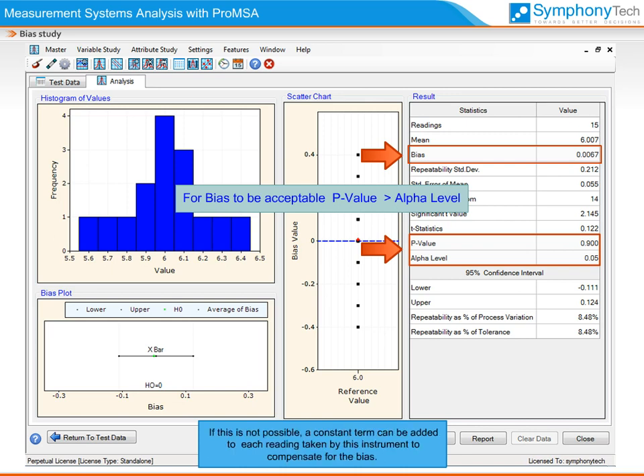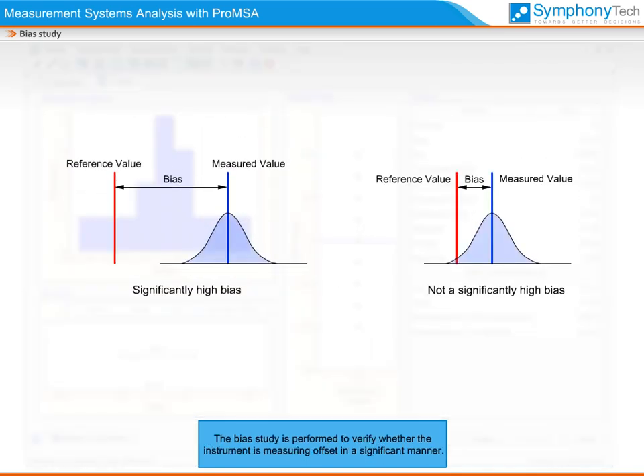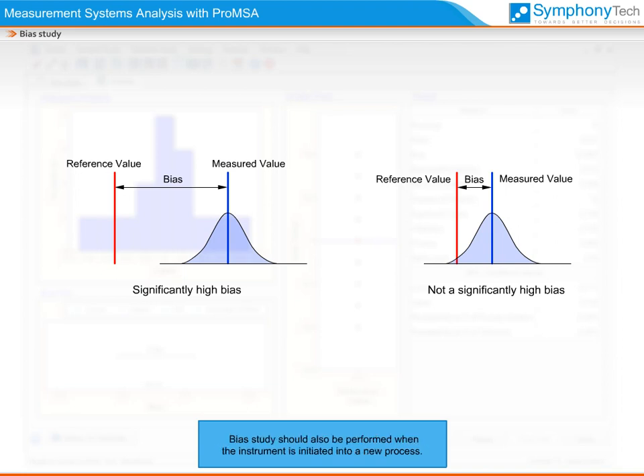If calibration is not possible, a constant term can be added to each reading taken by this instrument to compensate for the bias. The bias study is performed to verify whether the instrument is measuring offset in a significant manner. The test also reflects on the calibration state of the instrument and establishes its suitability to measure the process. Bias study should also be performed when the instrument is initiated into a new process.